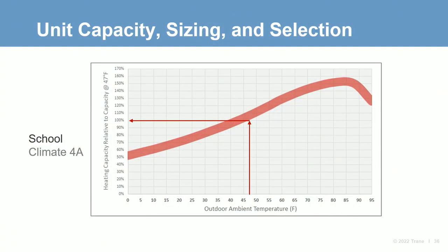Because of the dramatic change in air-to-water heat pump heating capacity at low outdoor air temperatures, a careful analysis of unit capacity, sizing, and selection is required. A commonly used AHRI rating point for heating capacity is at 47 degree outdoor air temperature. However, the outdoor air design heating temperature is typically much colder, resulting in a substantial capacity adjustment.